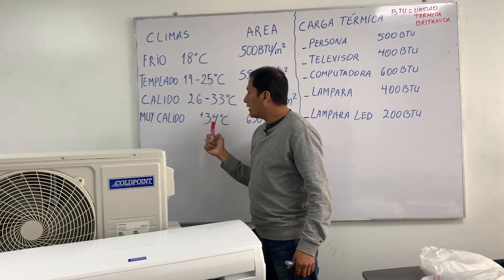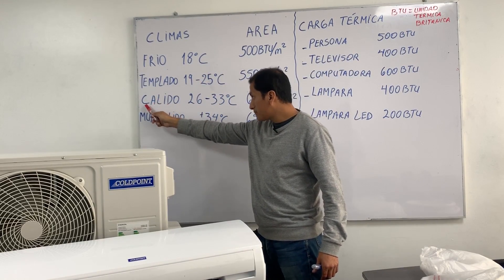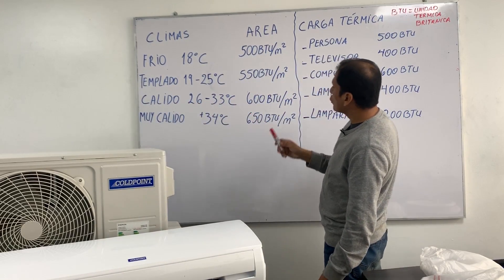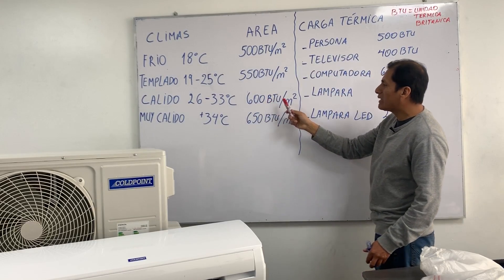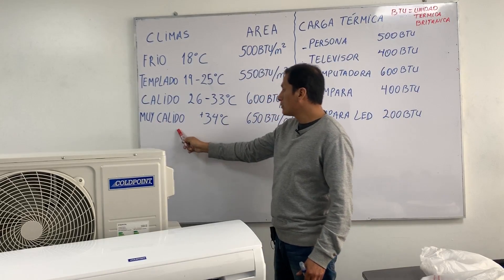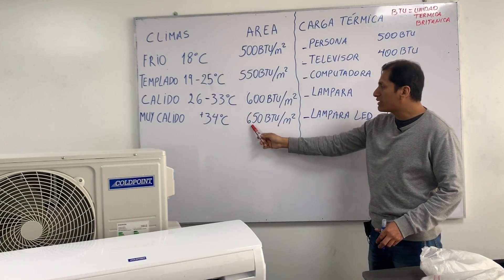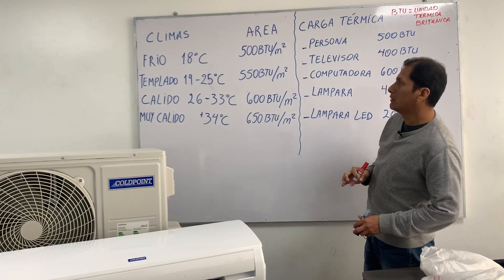Having climate as a reference, according to the table, for a hot climate — which is 26 to 33 degrees Celsius — we assign a value of 600 BTU per m². For a very hot climate — greater than 34 degrees Celsius — we assign a value of 650 BTU per m².